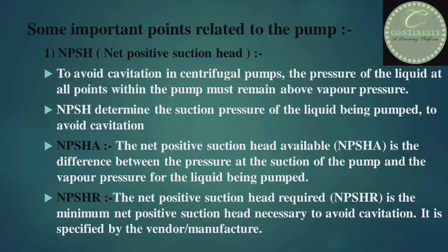Now about NPSH — net positive suction head. To avoid cavitation in centrifugal pumps, the pressure of the liquid at all points within the pump must remain above vapor pressure. NPSH determines the suction pressure of the liquid being pumped to avoid cavitation. There are two terms: first, NPSHA — net positive suction head available — and second, NPSHR — net positive suction head required.